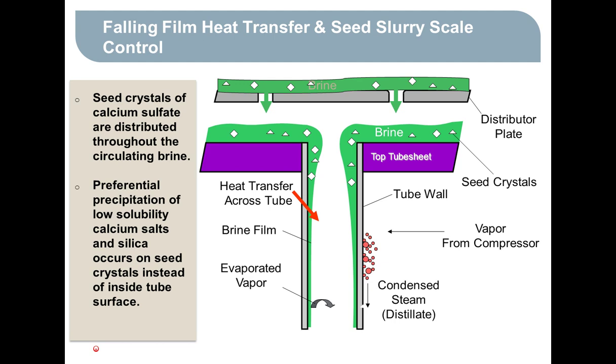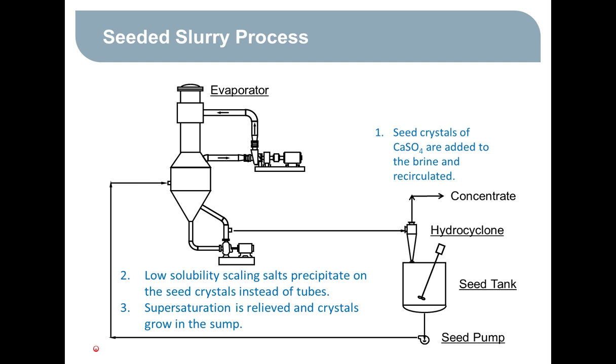The question might occur to you, well, how do the seeds get in there in the first place? And they're deliberately placed in a seed tank, which you see here, which is connected to the evaporator. And initially, when we start the system up, we actually put calcium sulfate into the seed tank and mix it up with water and pump it into the evaporator so that the system has a bunch of seed crystals in it when we first start it up. And then we have a hydrocyclone, so when we pump the concentrated brine out of the evaporator, we can spin those seed crystals back in the hydrocyclone, put them back in the seed tank and pump them back into the evaporator. So we don't lose all of the seed crystals out the back end of the system.